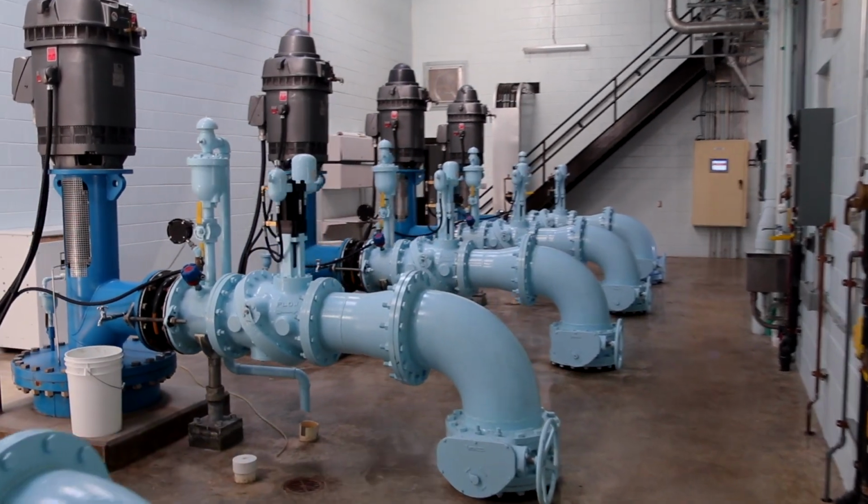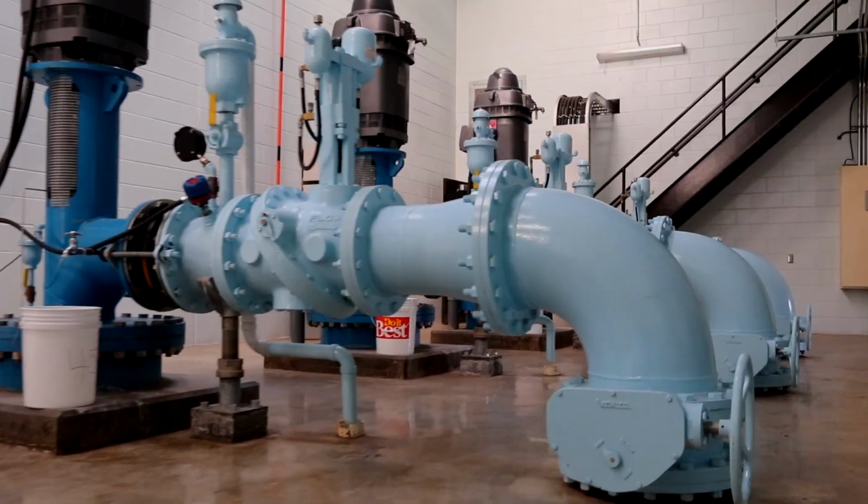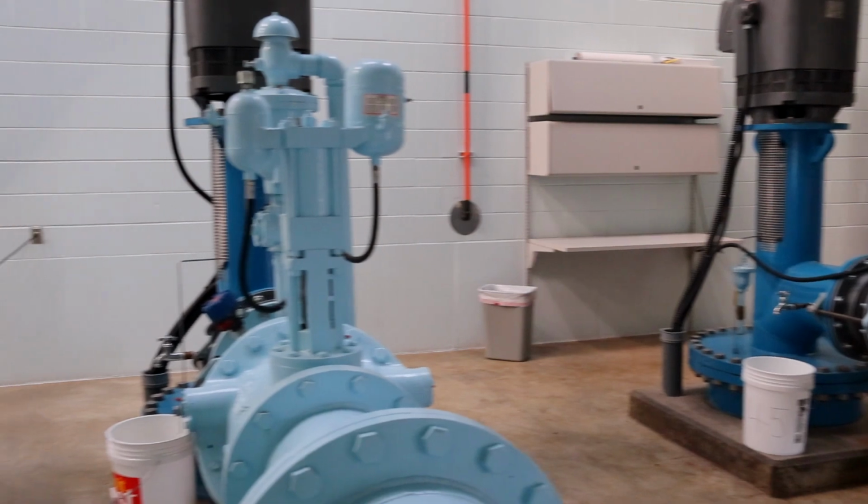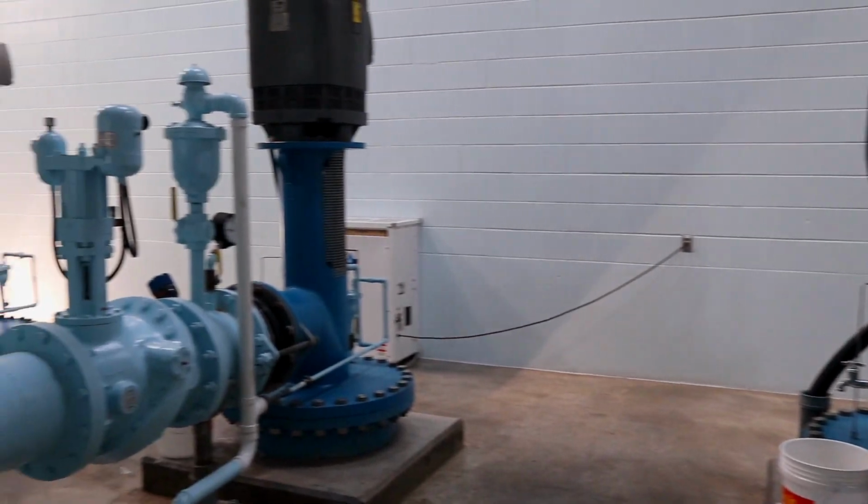Yeah, absolutely. Thanks, Tim. So, City of Rockford, we have 815 miles of water main spread throughout our city. We operate 4 different hydraulic pressure zones, and we have 25 remote unit well facilities. Within those facilities is where the treatment lies. We have 6 radium treatment plants where, similar to what you mentioned, we're using sodium permanganate and manganese sulfate, and we're batching those into a 1% day tank solution.